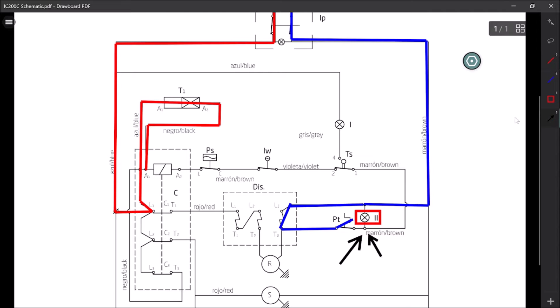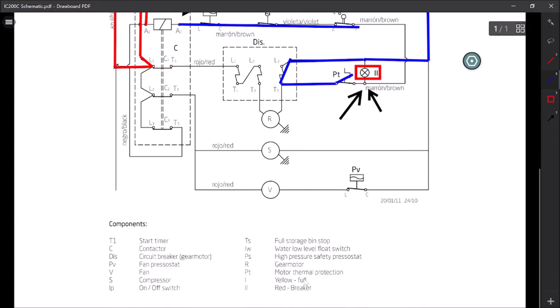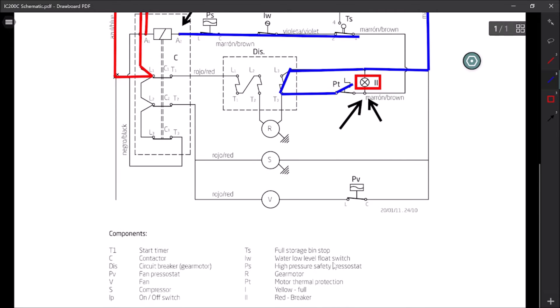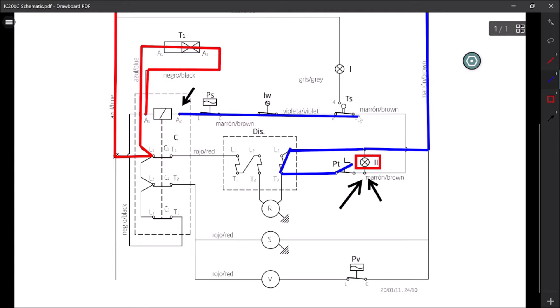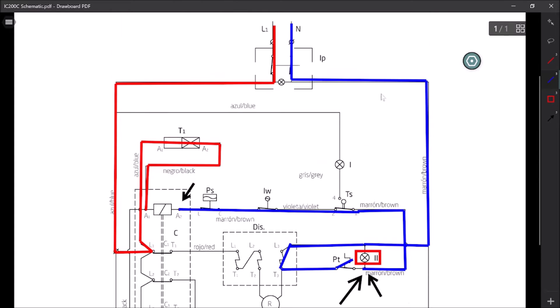So how does A2 get hot? This is where things get really confusing. Following A2: we come through PS, LW, and TS, which is our safety loop - high pressure pressostat, water low level float switch, and TS is our bin-full sensor. If this safety loop is closed, we come back around, down through here, through the light, through the switch, and loop all the way back around to the neutral. So this neutral is actually feeding our coil.